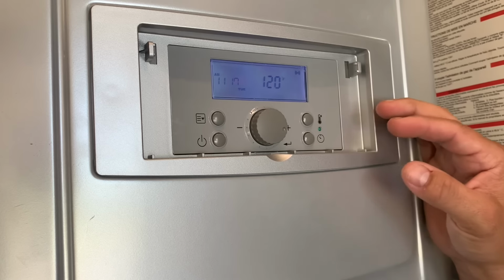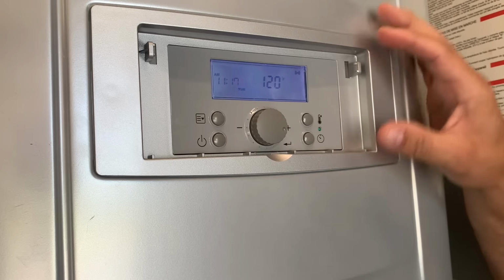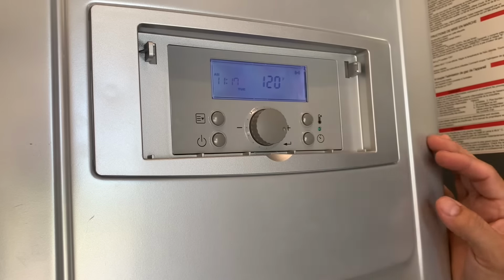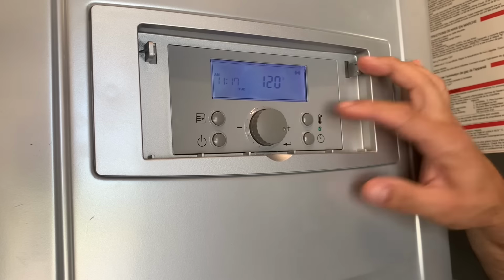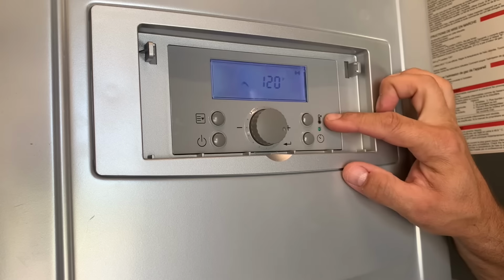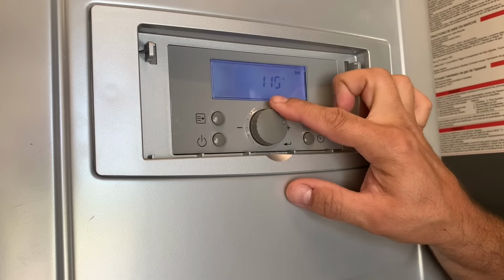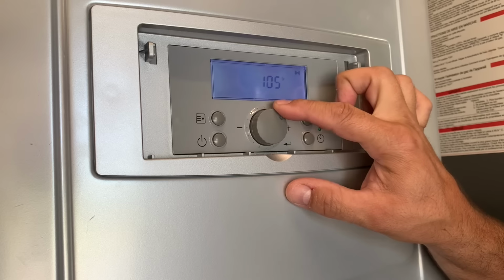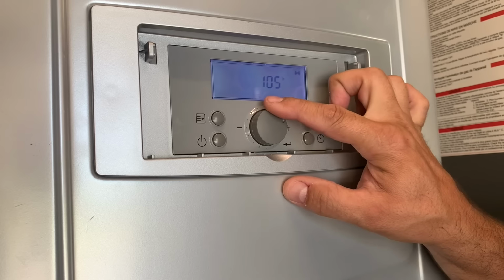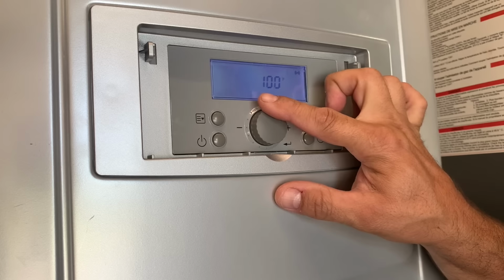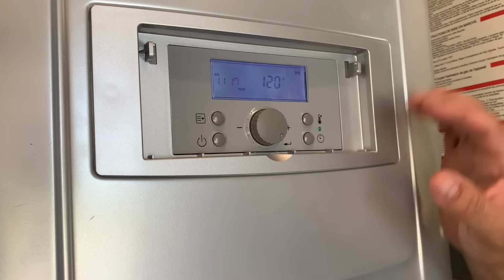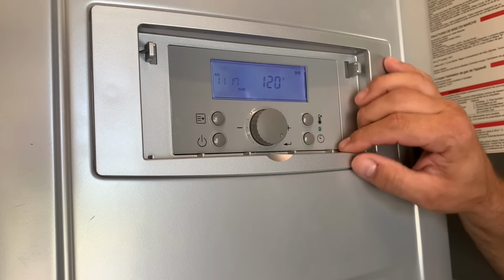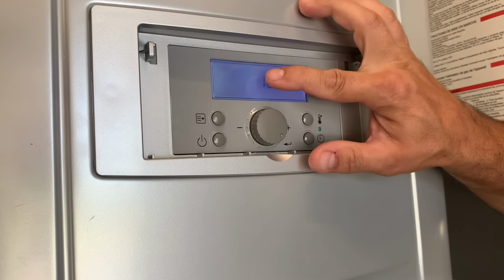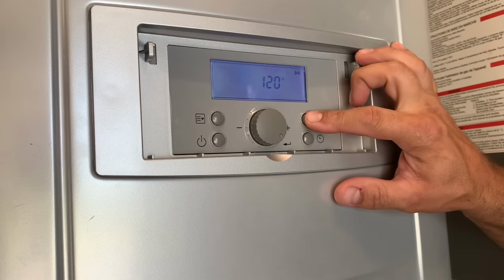Now we're going to change the set point of the water temperature. The default setting is 120. With the power on, if you want to adjust your temperature, press the little temperature button and then you can adjust it down or up. It's going to bounce around at 5-degree increments all the way up to 120, down to 100. Now if you want to go above 120, all you do is tap the button. You'll see the icon flash. Hold that button down.